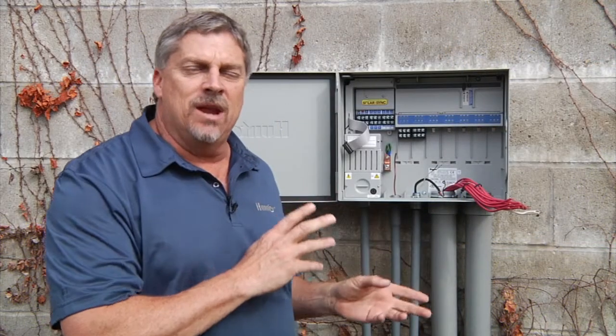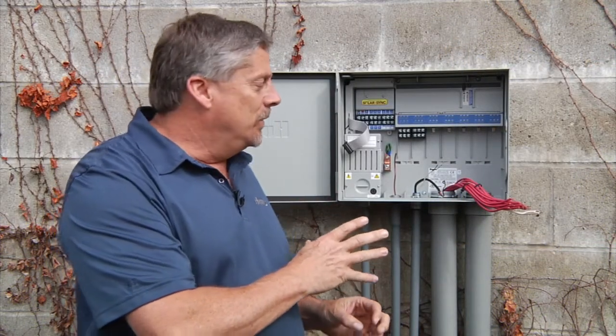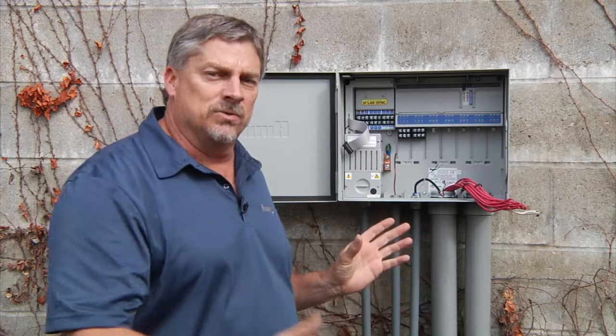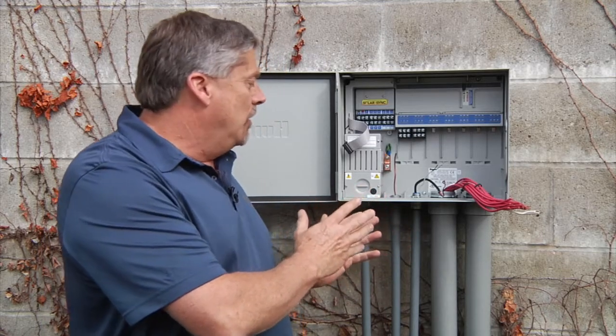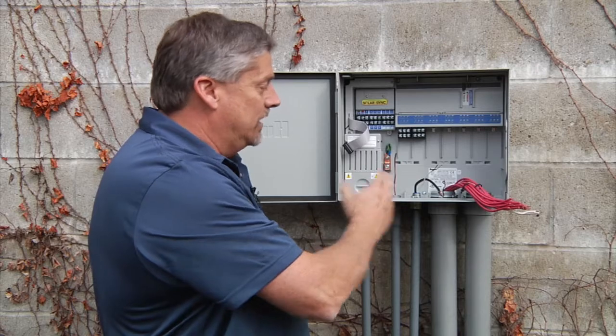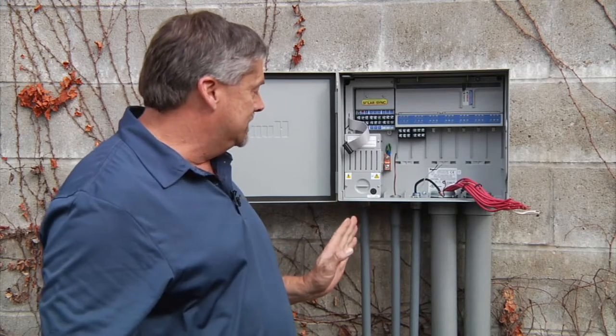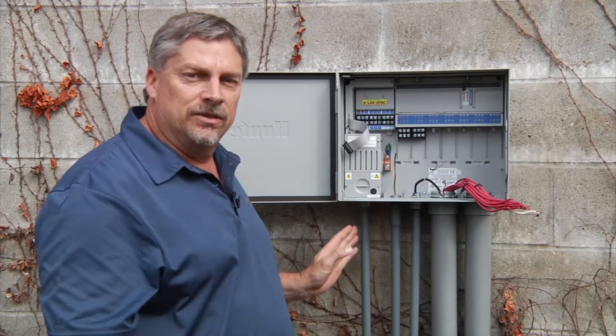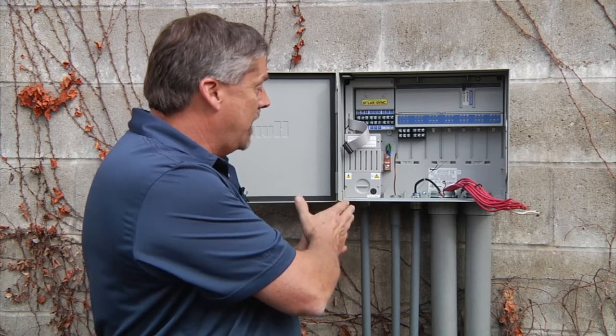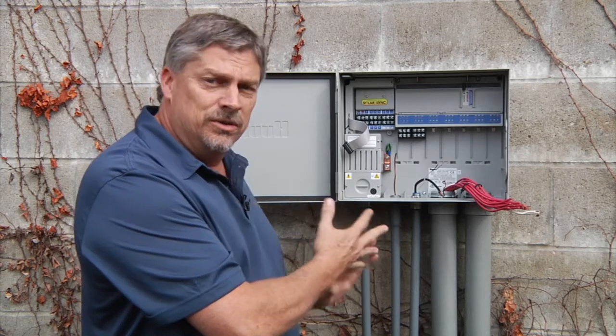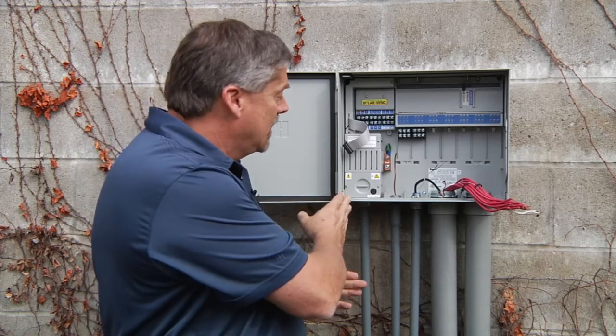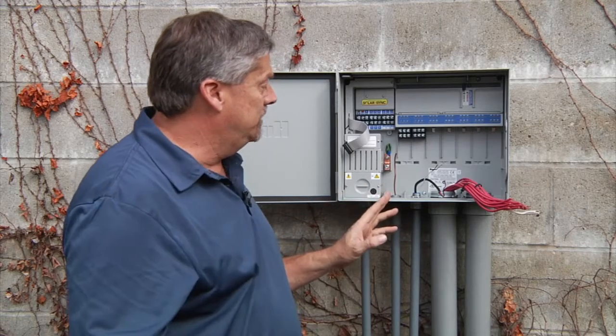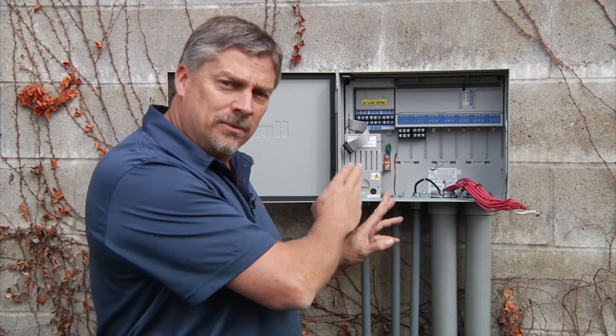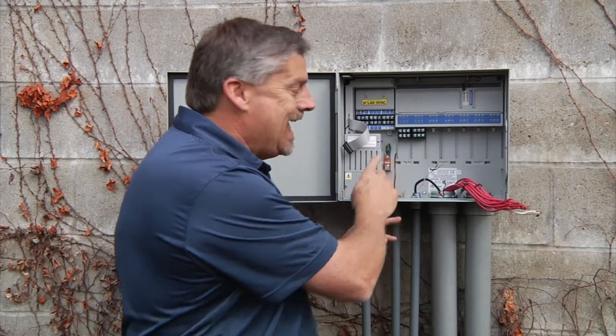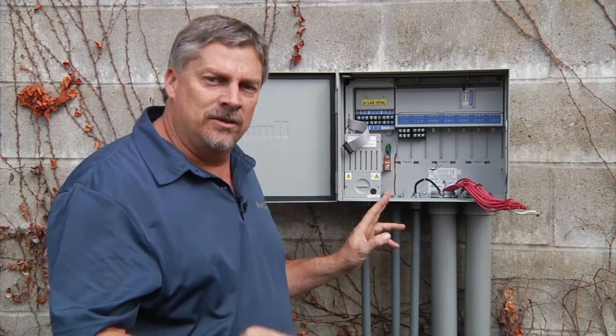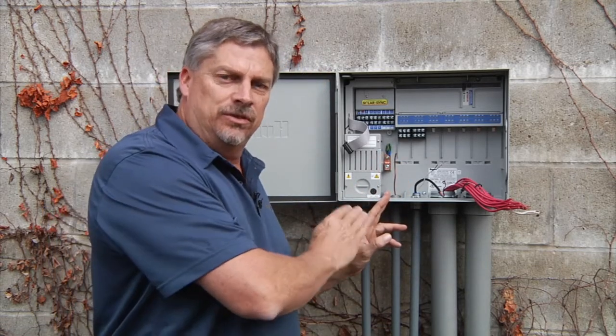So at this stage of the game, we have the controller mounted on the wall, we have the conduits installed, and all the wires ran up to the controller. We'll start talking about the wiring and the conduit here, and we'll start on the left-hand side. This is the 1/2 inch or 13 millimeter incoming power supply, be it 120 or 230, depending on your power source. And the next conduit over is going to be used for our grounding wire. That's the wire that goes from the grounding lug out to a grounding rod or a grounding plate. That's also 1/2 inch or 13 millimeter.